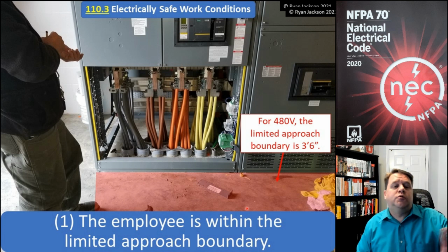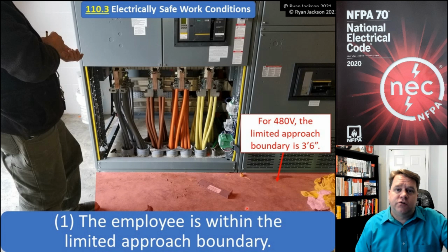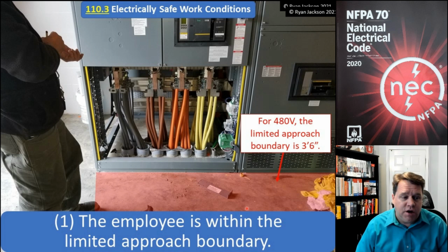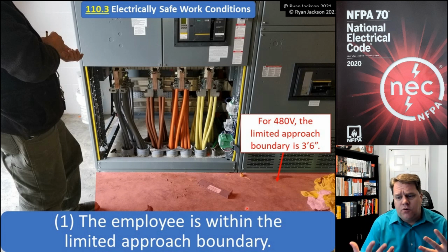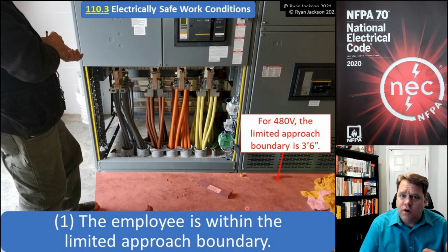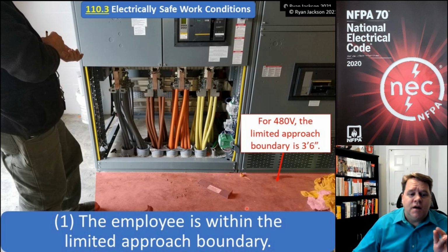Can you walk right up to a panel and turn on and off a circuit breaker in the NFPA 70E? Sure. Assuming that it's in normal operating condition, covers are closed and everything else, yeah, you can go up and touch the panel without putting on any PPE or without shutting anything off. What we're saying is if there's a shock hazard, such as the covers being removed, then we have a limited approach boundary, and we need to have an electrically safe work condition if you're within the limited approach boundary.